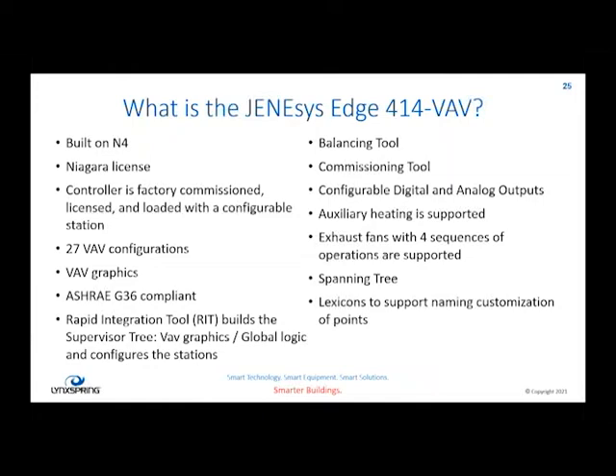Because our DOs are also configurable, we can do exhaust fans. We can support exhaust fans now. We have 4 different sequences of operations for exhaust fans. To connect the controllers together, instead of doing a home run to each controller, we use a spanning tree. So we can literally daisy chain the controllers together, bring the last one back around and make a loop out of it. We also have lexicons, which are going to be great for all of the applications out there that have to have customized naming. Every customer's got a different naming sequence. Vendors have different namings, so we support all that.